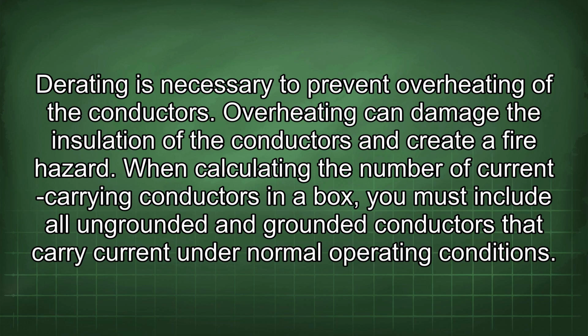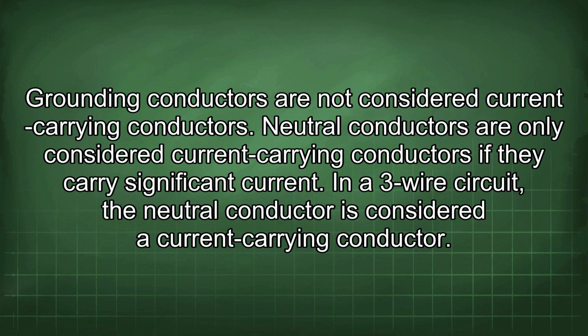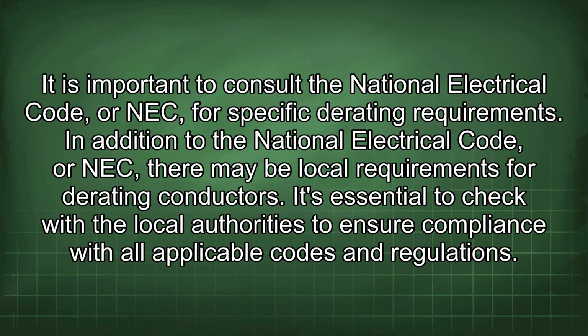When calculating the number of current-carrying conductors in a box, you must include all ungrounded and grounded conductors that carry current under normal operating conditions. Grounding conductors are not considered current-carrying conductors. Neutral conductors are only considered current-carrying conductors if they carry significant current. In a 3-wire circuit, the neutral conductor is considered a current-carrying conductor. It is important to consult the National Electrical Code, or NEC, for specific derating requirements. In addition to the NEC, there may be local requirements for derating conductors. It's essential to check with the local authorities to ensure compliance with all applicable codes and regulations.